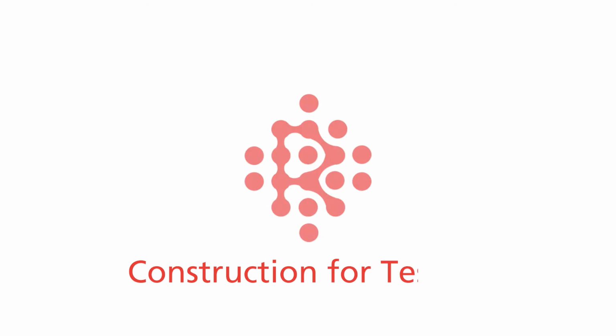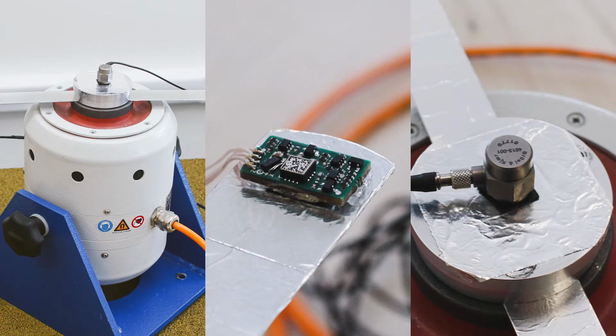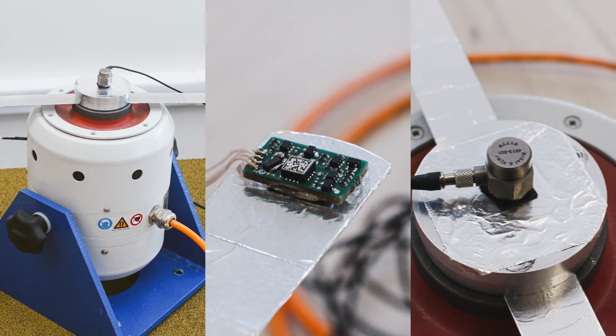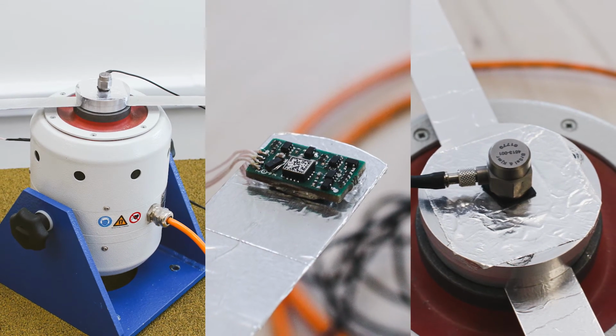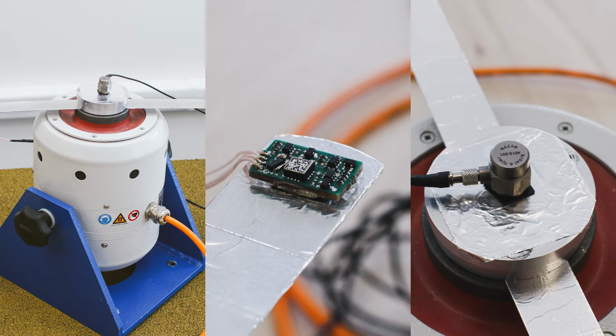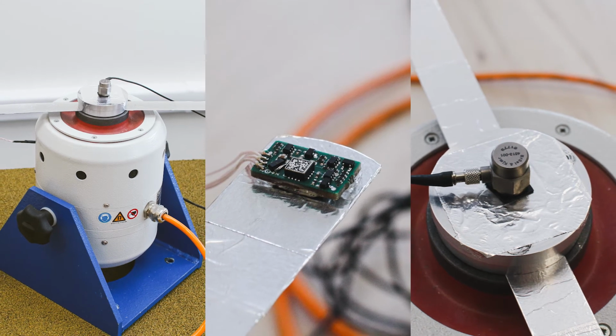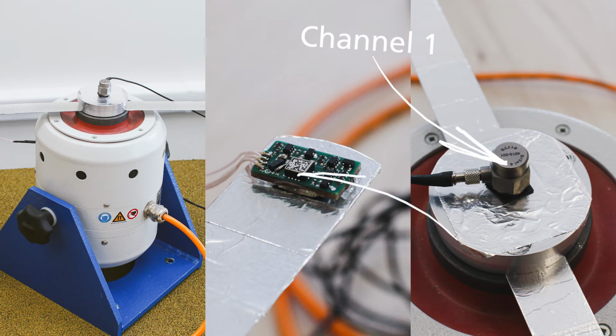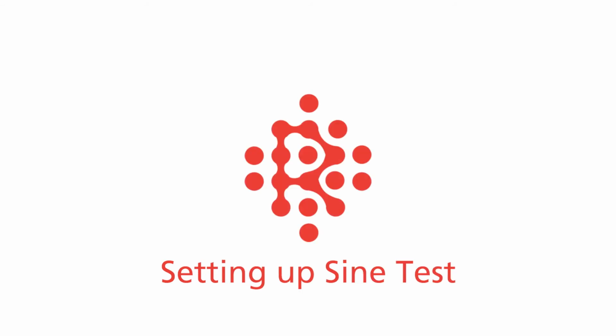Before we begin, let's discuss the construction we'll use for testing. We have assembled a model satellite from a thin metal strip attached to a shaker, and then put three accelerometers on both sides and in the center. The accelerometer in the center is connected to channel 1 on our vibration controller, while the sensors on either end are connected to channels 2 and 3. Now let's set up a sine test.